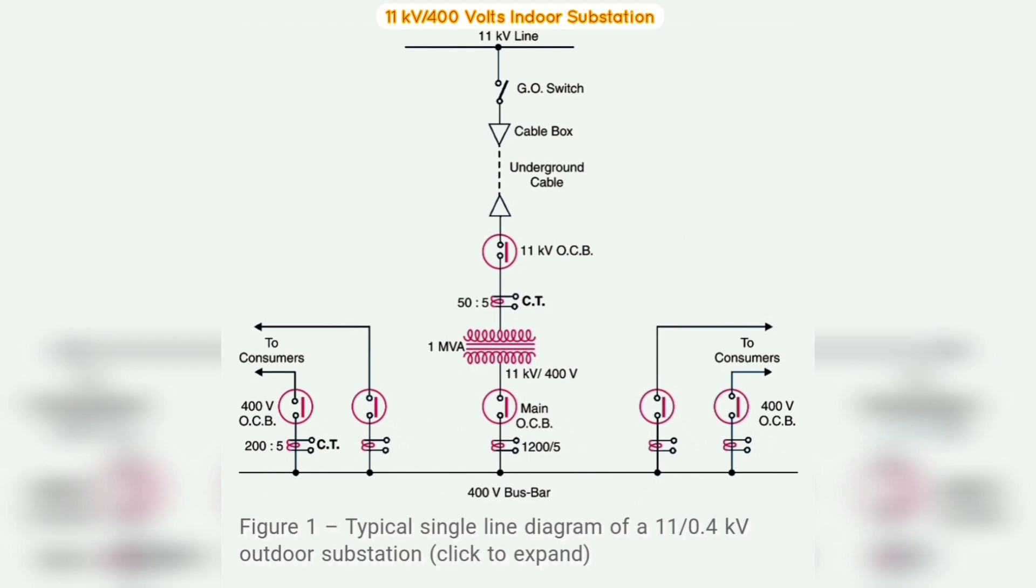The voltage between any two phases is 400 volts, and between any phase and neutral it is 230 volts. Next, we learn about the single-phase residential load is connected between any one phase and neutral, whereas three-phase 400 volt motor load is connected across three-phase lines directly.